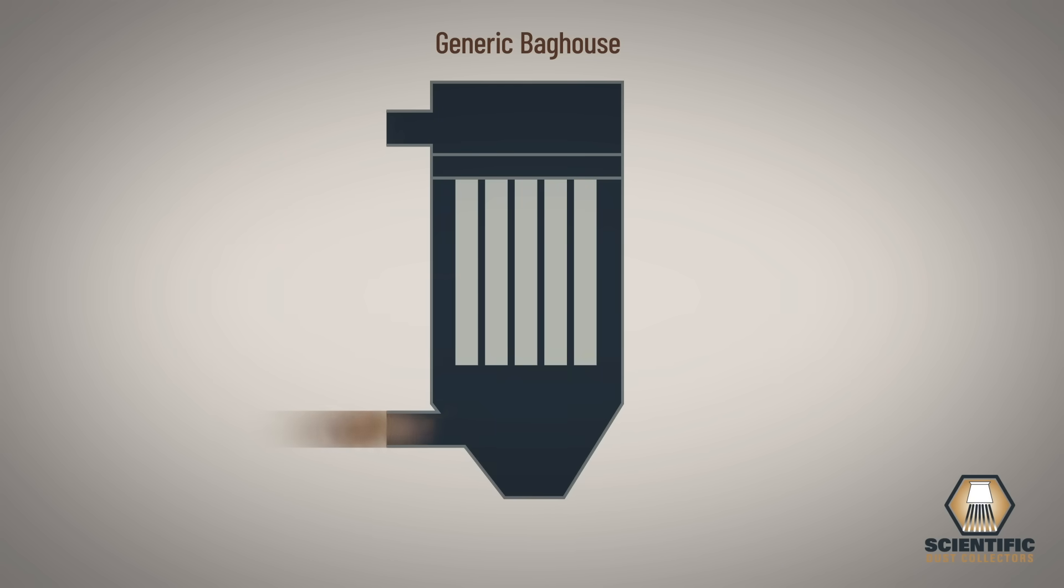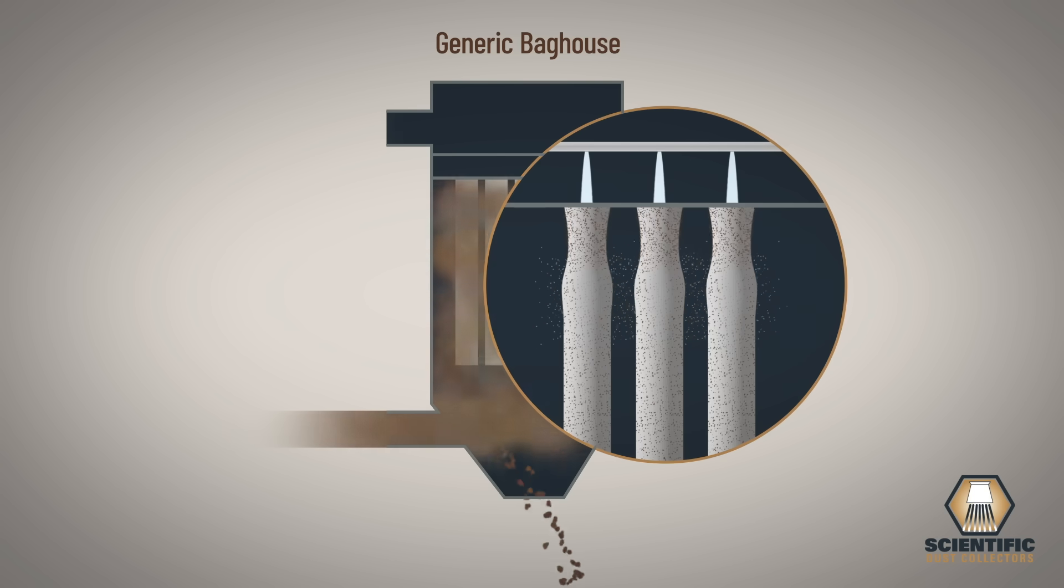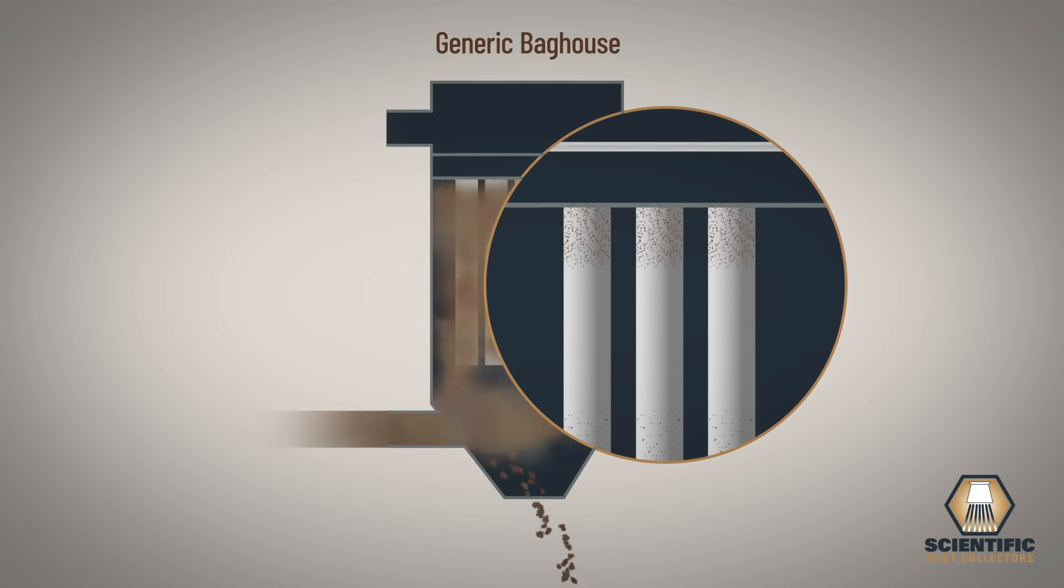In a generic bag house, dirty air enters the collector from the bottom at high velocity. This creates an upflow of dirty air in the collector and causes re-entrainment of dust on the filter media during the cleaning cycle.